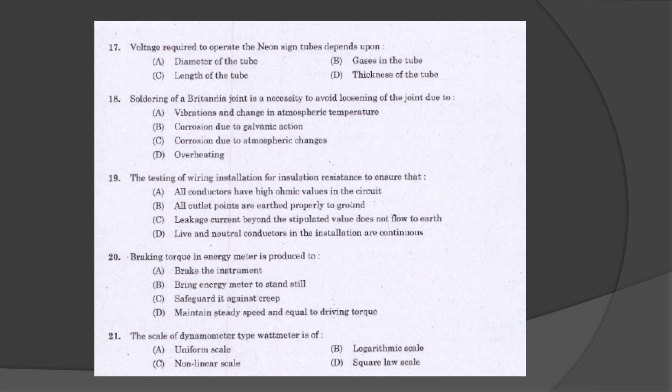The voltage required to operate the neon sign tube depends upon the length of the tube. Soldering of a Britannia joint is necessary to avoid loosening of the joint due to vibrations and change in atmospheric temperature. Testing of wiring installation for insulation resistance ensures that leakage current beyond the stipulated value does not flow to the earth.